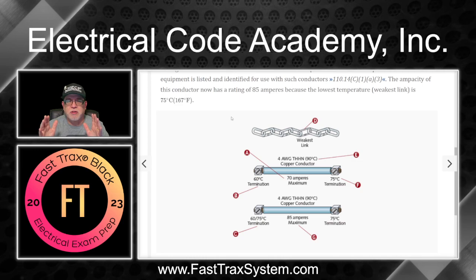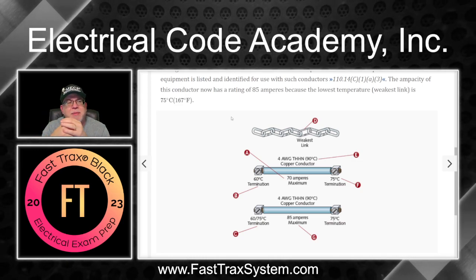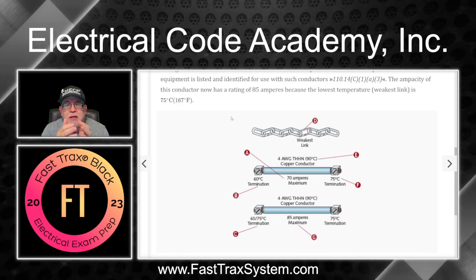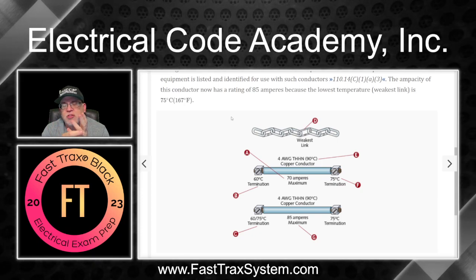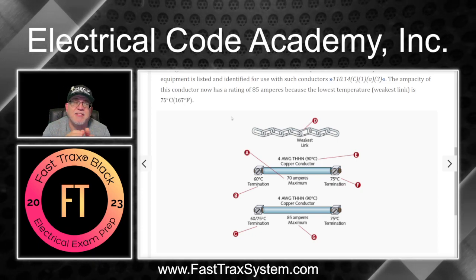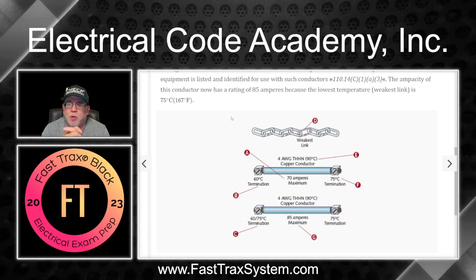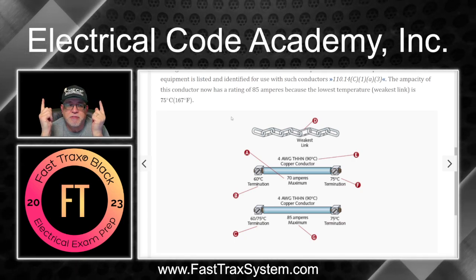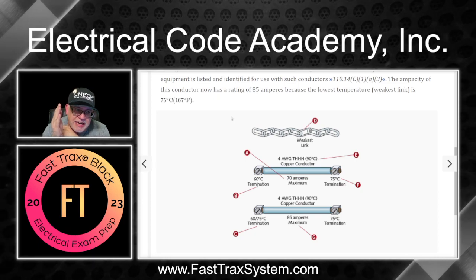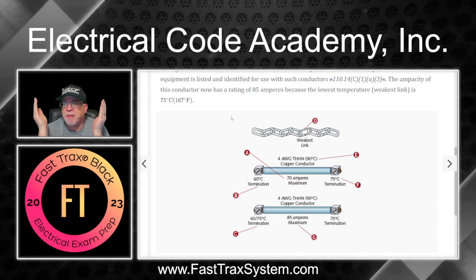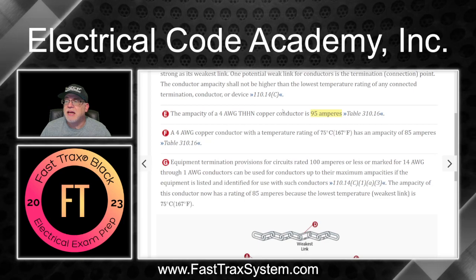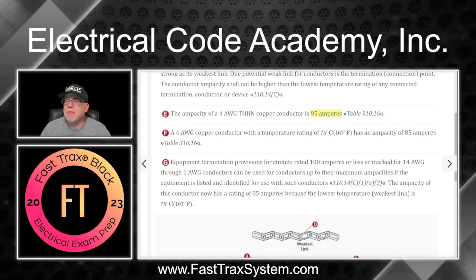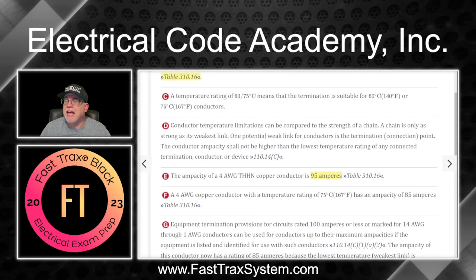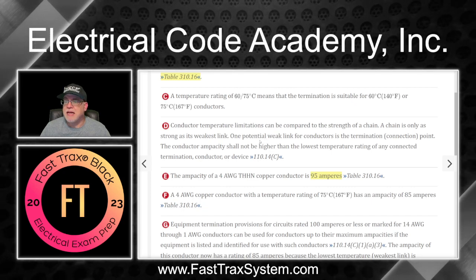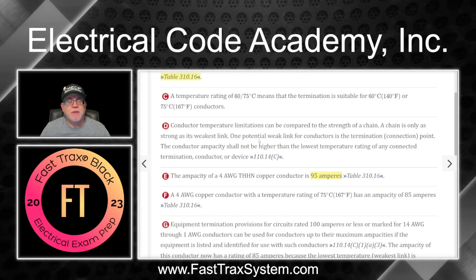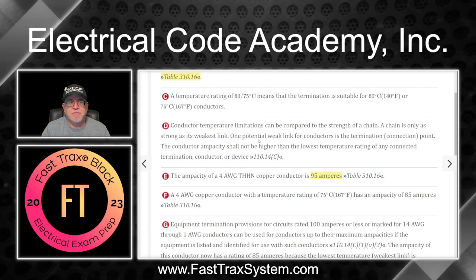It's just the conductor. But because we have these limitations based on the lugging, that's what's going to limit us to 75 degrees C. Now, that's not to say that there aren't applications out there where the lugs might be 90 degree rated and the conductor's rated 90. And then could I use it at its full ampacity? Could I use it at the maximum ampacity for that conductor? Absolutely, I could. 95 amps. If everything is rated 90, no problem.